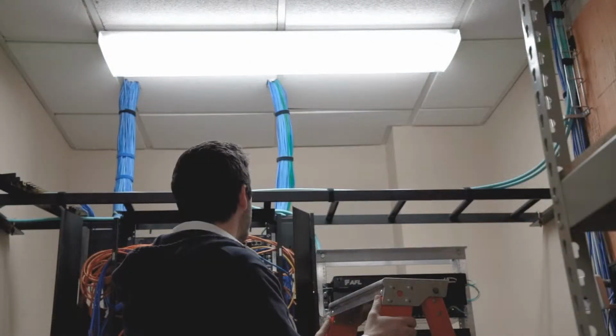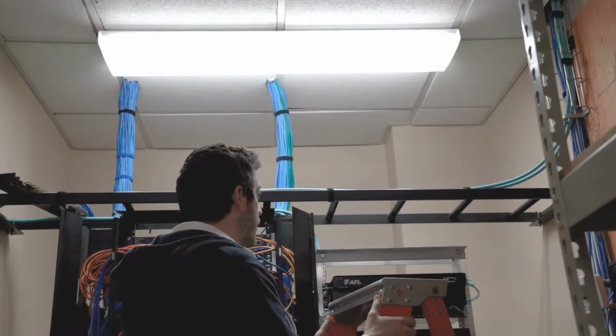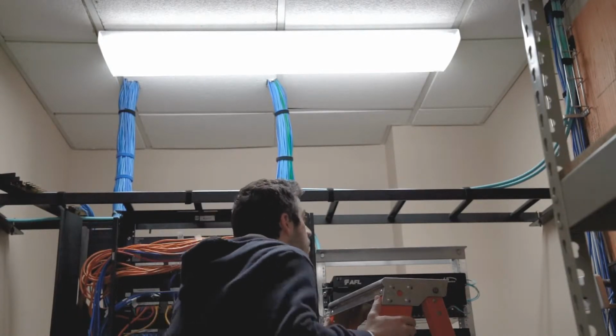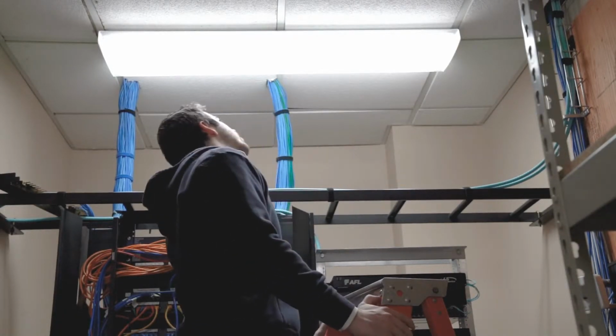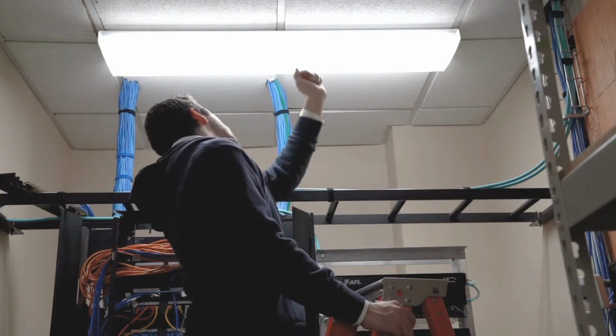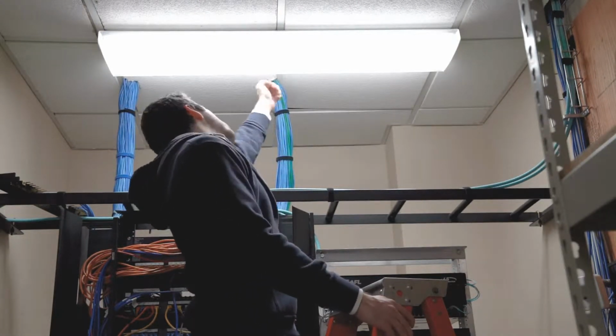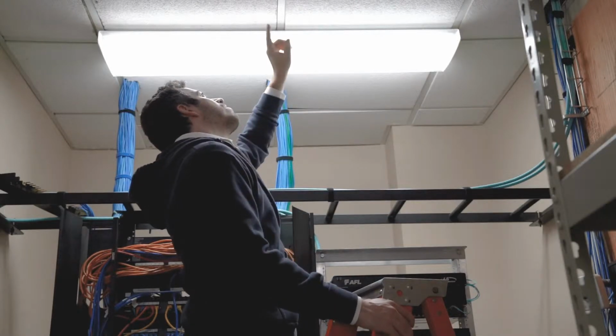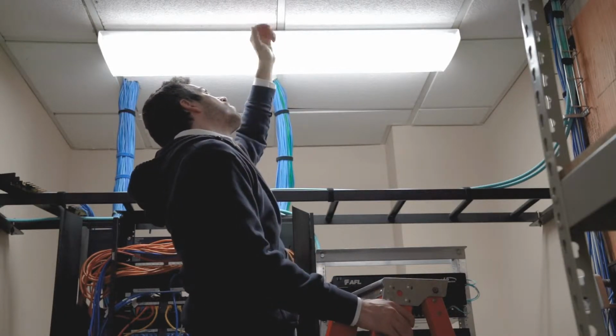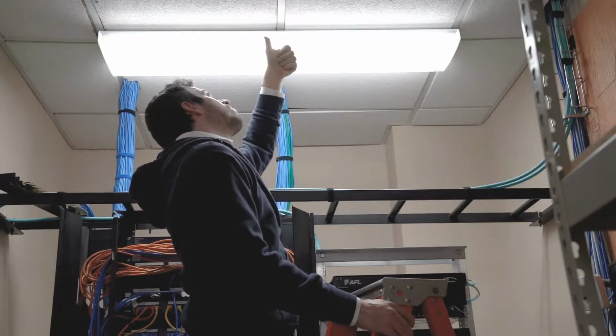Here's an example of poor sensor placement. There is a sensor on the other side of this fixture which is not even visible from the hallway. The sensor can't see anything and is not placed in a location where it can properly do its job. It cannot detect motion due to its position. If the sensor had been installed here instead, it would be able to detect the motion in the space.